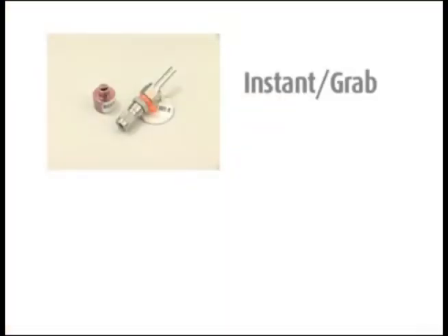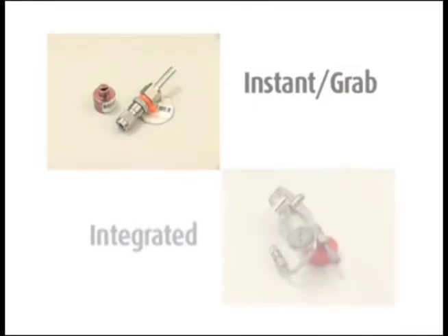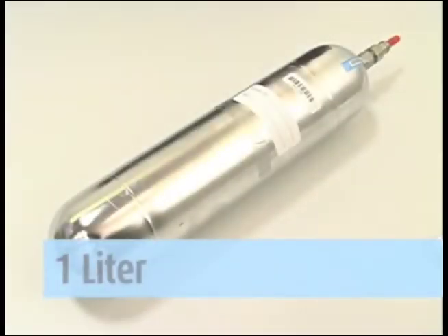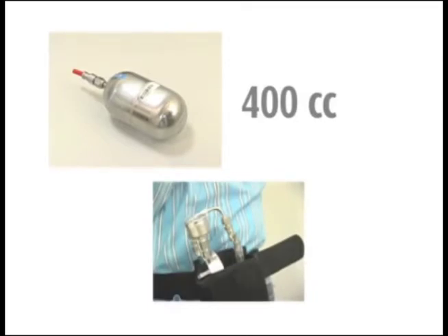You can also have two different sampling setups, instant grab or integrated. Either size can be used for either type of sampling. However, if you will be sampling for more than 8 hours, you should use the 1 liter size can. And if you are going to take a personal exposure sample, you should use the 400 cc size with the tubing and belt holster combination.